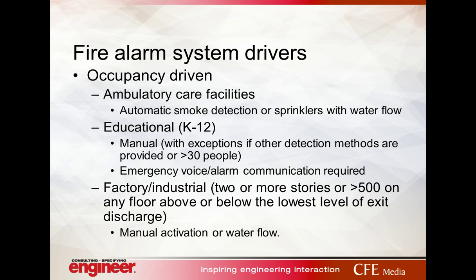Educational occupancies have requirements that have changed over the last few code cycles. In general, there is a requirement for manual activation of notification as well as a requirement for emergency voice alarm communication systems with speakers. A change in the IBC allows an emergency voice alarm communication system to communicate other emergency messages — so within a K-through-12 facility, if that voice system is designed appropriately, it can be used not only for fire evacuation but also for other emergency messaging. For factory and industrial buildings, depending on size and occupant count, fire alarm and notification requirements apply when exceeding one story with occupant loads greater than 500 above the lowest level of exit discharge.